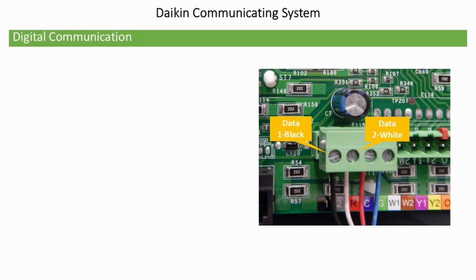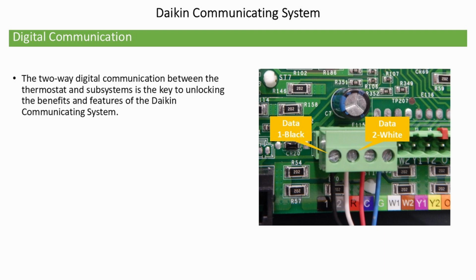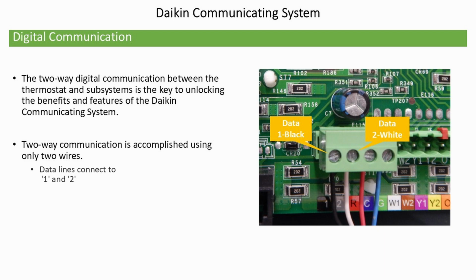The Daikin communicating system. Digital communications. The two-way digital communication between the thermostat and subsystems is the key to unlocking the benefits and features of the Daikin communicating system. Two-way communications is established using only two wires. The digital communication data wires connect to 1 and 2. R is 24 volts AC hot. C is 24 volts AC common.